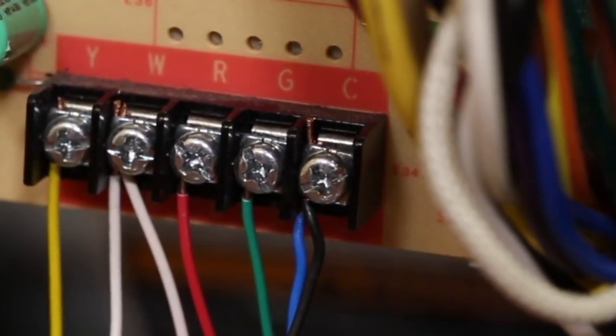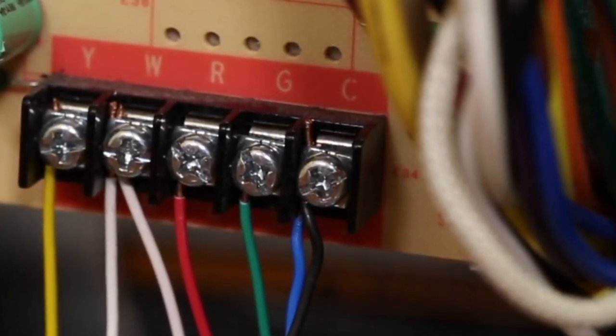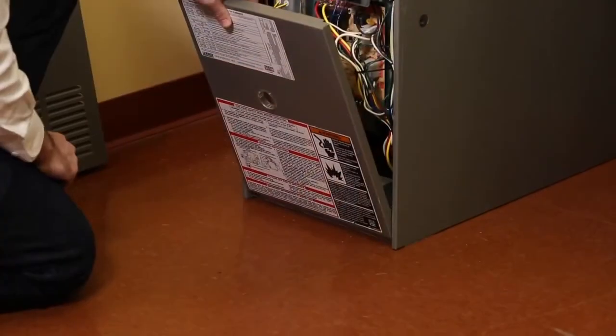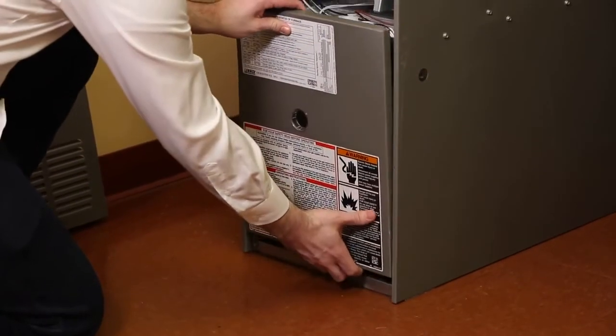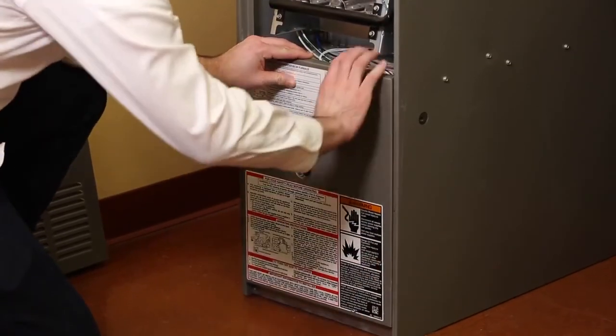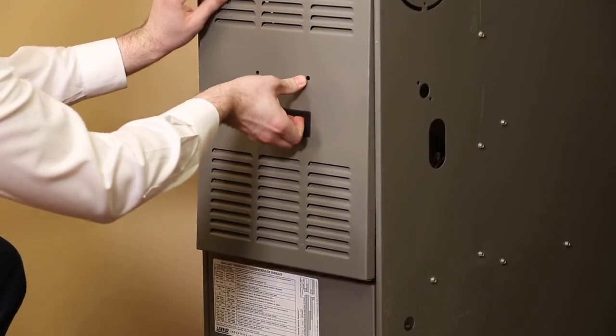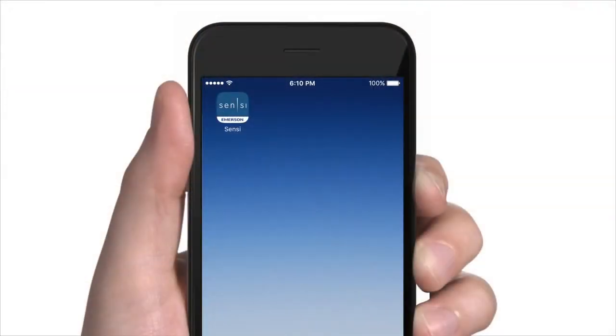If this is the case, simply add your new wire, but be sure to leave the existing wire or wires connected as well. Once secure, replace your furnace door panel. Be sure to replace it correctly, as most furnaces will not operate unless the door is on correctly.